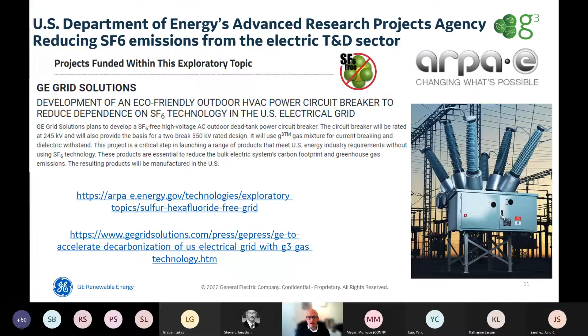We are developing a couple of first designs for lower performances with g3, or for dead tank breakers. But based on the specificities of the IEEE standards, the fact that it's 60 Hertz, the fact that we have to go to minus 30 degrees, there are some very specific performances in the IEEE standard versus the IEC one that make it more difficult to develop and successfully type test.